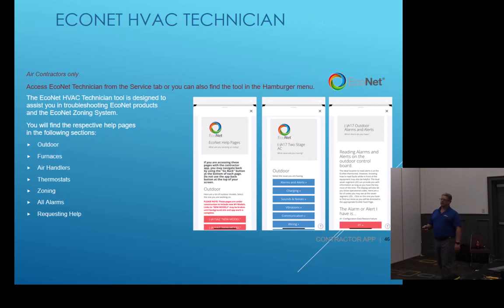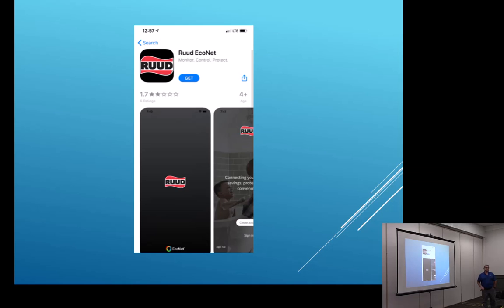Also, this is where we talked about O for outdoor, F for furnaces and air handlers, T if it's a thermostat alarm, Z for zoning, okay? A for all alarms. Also, you've got little codes outside on the board. It'll say D1 or whatever, so you can get your alarms and alerts, and it'll also tell you what the codes are out on the outdoor board, okay? I really like the EcoNet alarms, though. They really get you more dialed in on the information that you need and what the possible causes are. So we're going to go over our EcoNet stat, okay? The EcoNet stat is really the way to go.